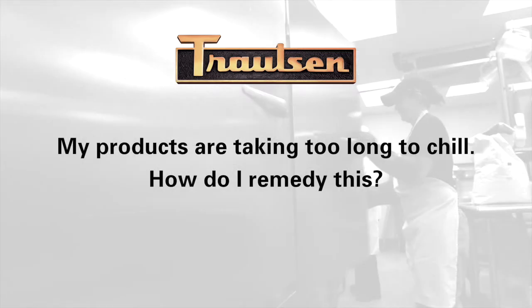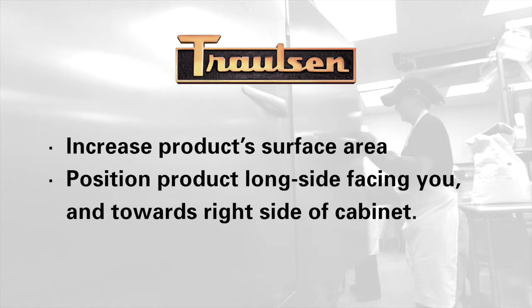My products are taking too long to chill. How do I remedy this? Most issues related to chill time are operational. The easiest way to decrease chill times is to increase the surface area relative to the total volume of the product. This will reduce the chill time, as will reducing the depth or size of the product.